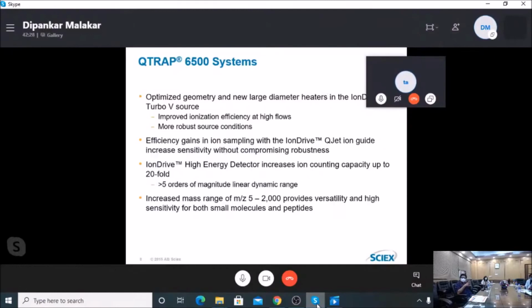There are efficiency gains in ion sampling with the IonDrive QJet ion guide, increasing sensitivity without compromising robustness. Ion drive, this new source, and the high energy detector increase the ion counting capacity up to 20-fold, with greater than 5 orders of magnitude linear dynamic range in the instrument. This higher dynamic range is good for quantitation, from low level to high level we can quantitate the analyte. The mass range is capable of 5 to 2000 m/z scale, which provides versatility and high sensitivity for small molecules as well as peptides, because peptides fall in the higher mass range.